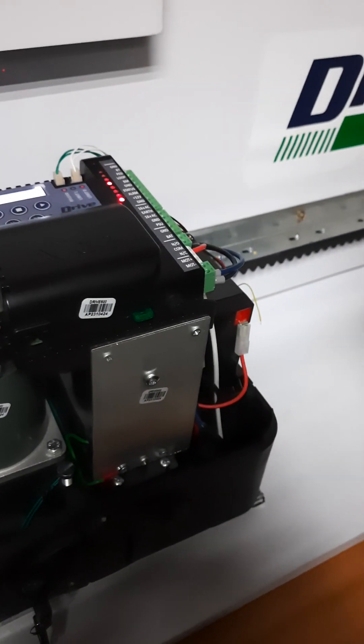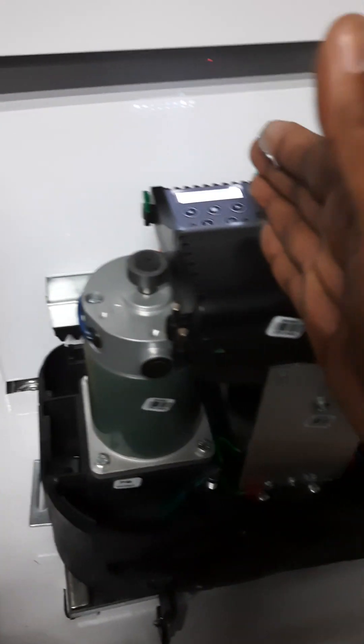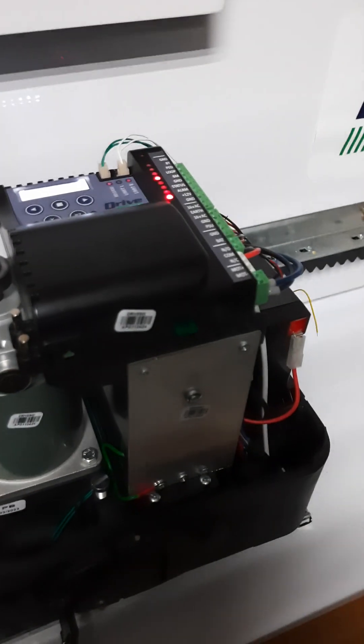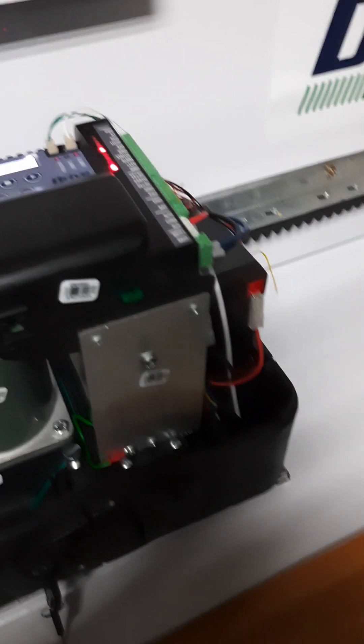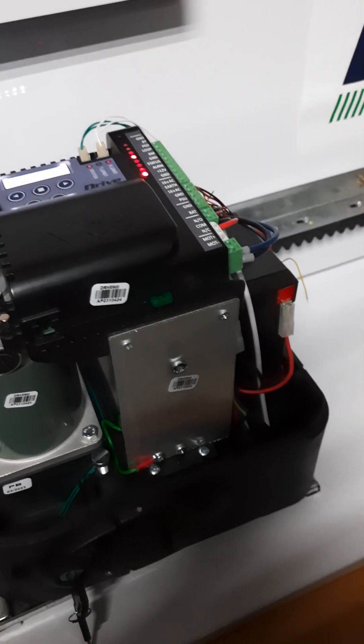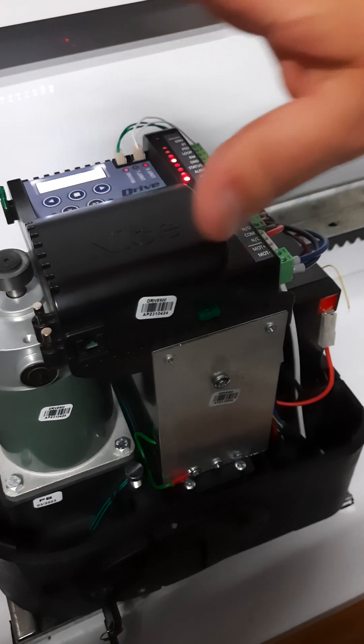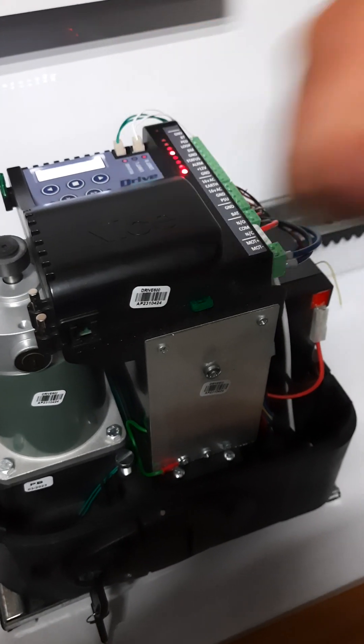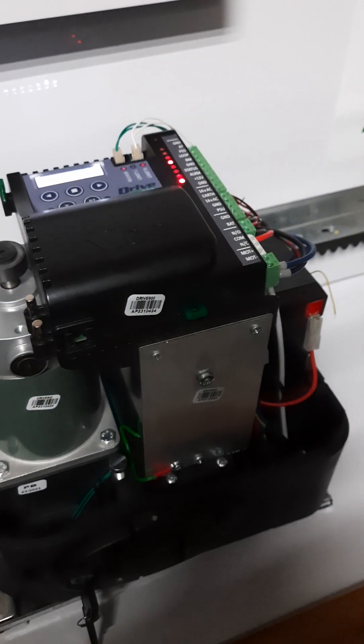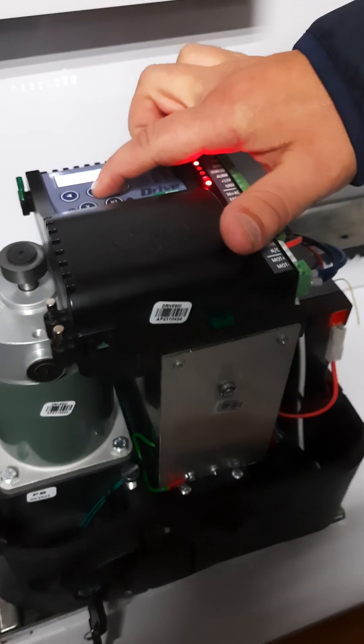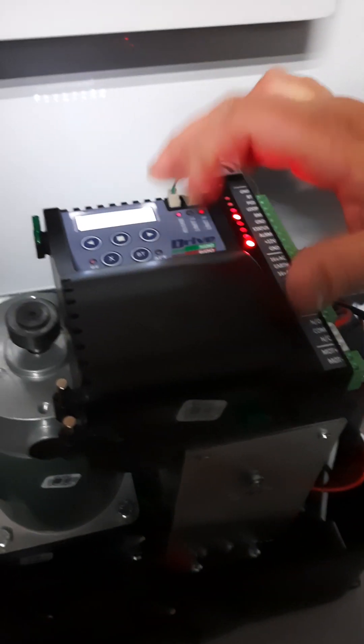And the beams have to activate? To the beams? Like auto-close how many minutes, 15 seconds? Yes. So you can activate the beams on their own. It doesn't have to be connected to the auto-close. If you just want it for safety. But our control card is designed in such a way that if you activate auto-close, it will automatically activate the safety beam as well. So all you need to go and do is just to set the time in the auto-close menu. So here we can go back to mode. There is the beam. As long as the auto-close is enabled, you won't be able to disable that beam.